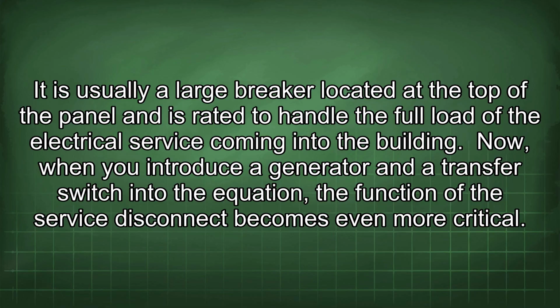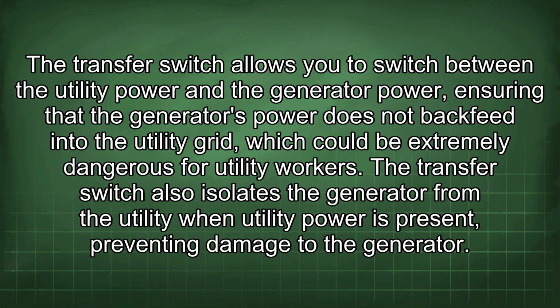Now, when you introduce a generator and a transfer switch into the equation, the function of the service disconnect becomes even more critical. The transfer switch allows you to switch between the utility power and the generator power, ensuring that the generator's power does not backfeed into the utility grid, which could be extremely dangerous for utility workers. The transfer switch also isolates the generator from the utility when utility power is present, preventing damage to the generator.